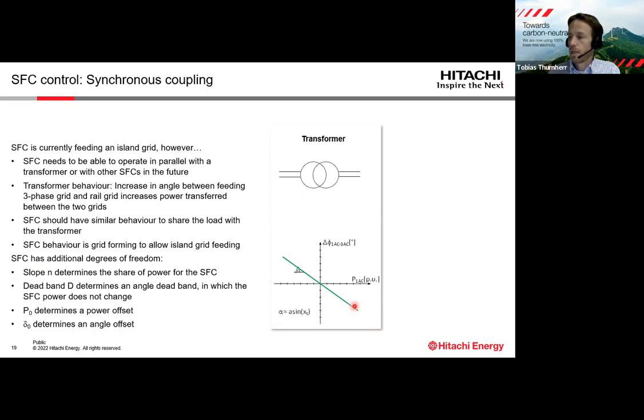So we can, in a simplified way, show the behavior of the transformer on this diagram that shows on the y-axis the angle between the single phase and the three-phase grid, and on the x-axis the power that flows through the transformer. We can show the behavior in an approximated way, valid especially around a very small angle, with a line that is crossing 0 here. And the line basically means that if the angle of the railway voltage is leading the angle of the three-phase grid voltage, then power is transferred from the single-phase grid towards the three-phase grid. And the more the angle is leading, the more power is transferred. The slope of this characteristic depends on the impedance of the transformer.